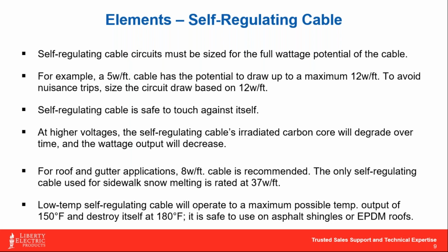So it'll give you plenty of output. And conversely, if we look at 208 supply voltage, we're derating that cable a little bit. So again, instead of 8 watts a foot, maybe we're putting out something more like 6.7 to 7 watts a foot, which is important because one of the things that we certainly try to emphasize during the installation process or even in the design process is to take a proactive voltage reading and find out exactly what our current is getting to that cable.